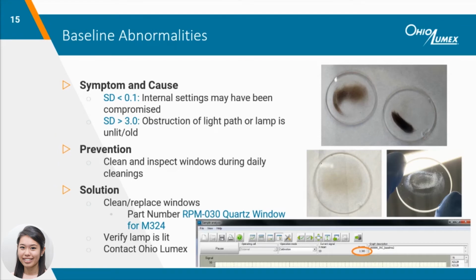The optics are a critical component of the instrument, and the quartz windows in the attachment are the most susceptible to getting dirty. Cleaning and inspecting the windows after every analysis day is a good practice to ensure the optical path is clear, which will yield more accurate results. A noisy baseline, defined by an SD of 3, reduces the sensitivity of your analyzer, which will make it difficult to quantify low-level mercury. A high SD is an indicator located at the top of the Rapid graph that the light path through the optical cell is obstructed, and most likely windows need to be cleaned or replaced.